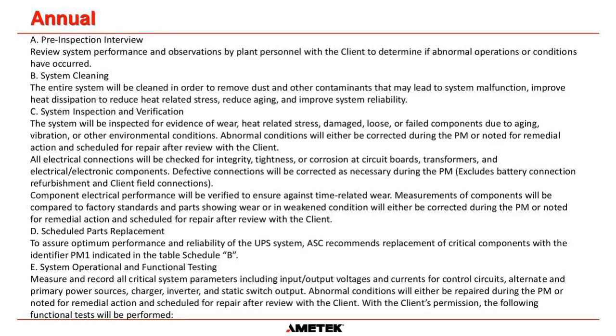So really, the most important things are that we do a system cleaning. Dust and other contaminants are actually one of the main causes of failure in any electronic system. So as part of our annual maintenance, we power the system down and we clean and remove dust and contaminants that could lead to malfunction. And then we also check for evidence of heat stress, damaged, loose, or failed components. And we not only do that by physically checking that, we call it the wiggle test. Our FSEs go in and they physically test each connection by wiggling it with their hand.